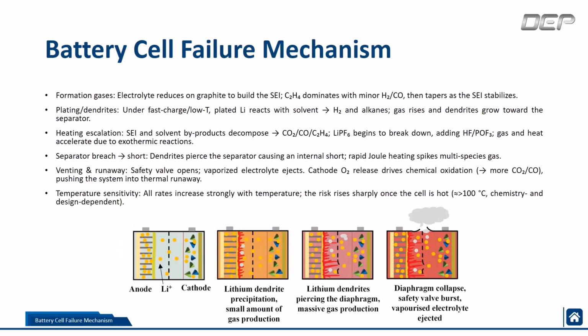So last here, before we start going into our sensor, we're going to touch base on the chemistry of what happens when the thermal runaway breaks down. Starting with a healthy cell, during the formation the electrolyte starts reacting with graphite and builds a protective layer called the SEI. This then breaks off a little ethylene, tiny amounts of hydrogen and carbon monoxide, and then it settles down.